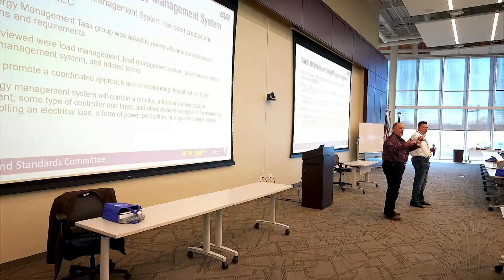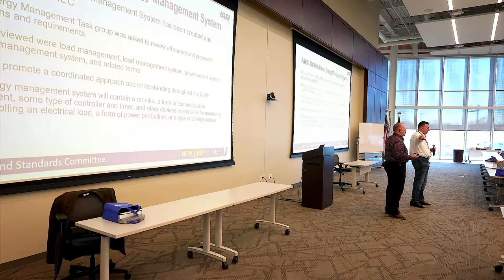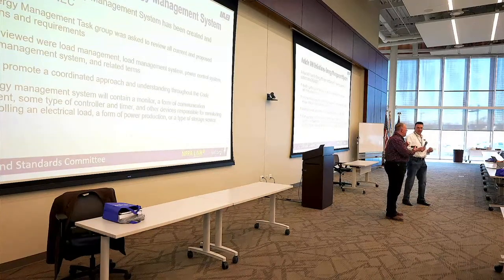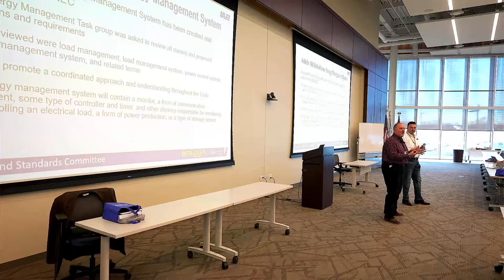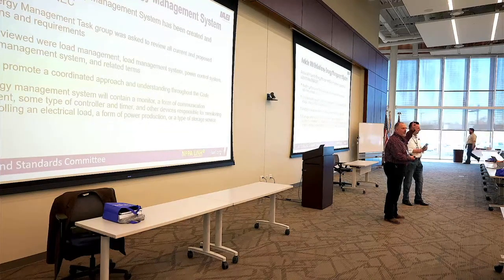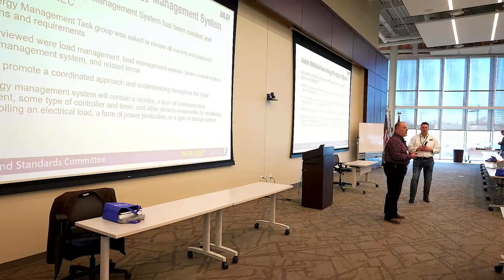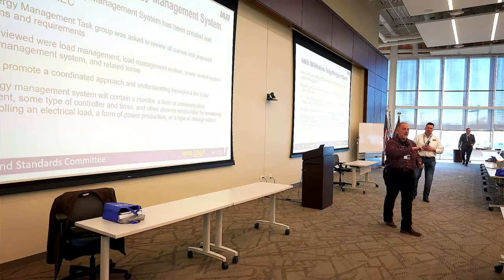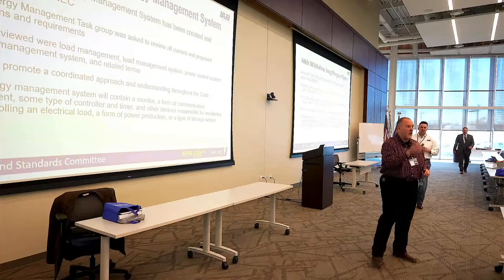If I have an alternative energy, an energy storage system, or whatever supplying power at the same time the utility is supplying power, I can add more loads because he may have a 200 amp breaker for him, right? I can let up to 200 amps from the utility, but now I have an additional amount of current coming from whatever's connected to this side, right? So now I can have current coming in from two different sources, and I can add more load to that panel board than the 200 amps that the main breaker is permitting to flow in. So now I can exceed the rating of the bus inside that panel board, because the bus is only rated for so much current.